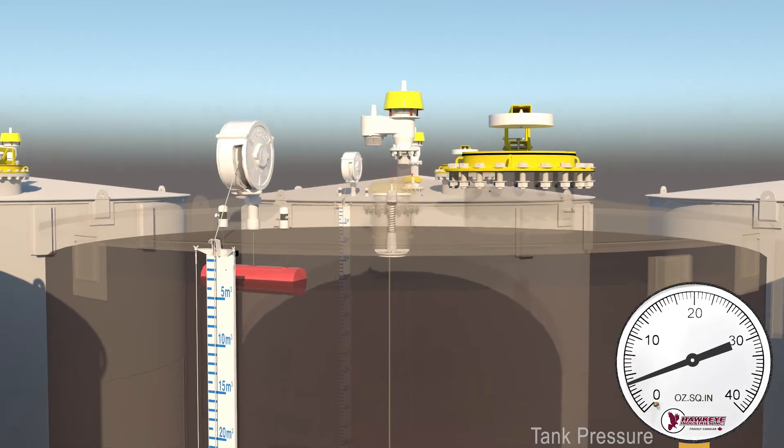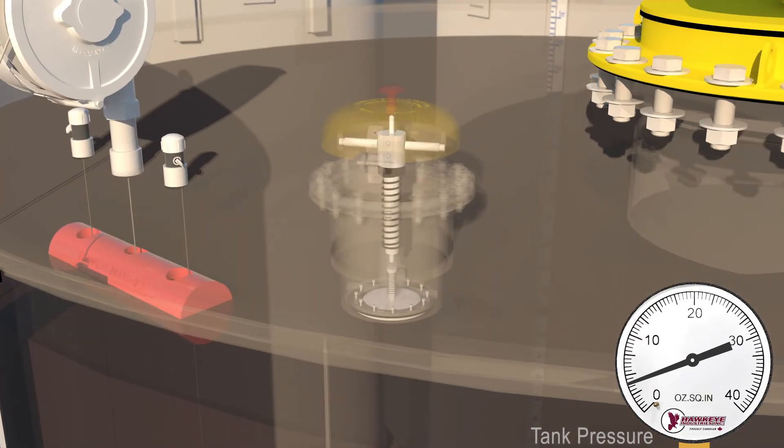In this example, the Marsh Hawk's pressure setting is set to relieve at 6 ounces per inch squared, and the vacuum setting is set at 0.4 ounces per square inch.